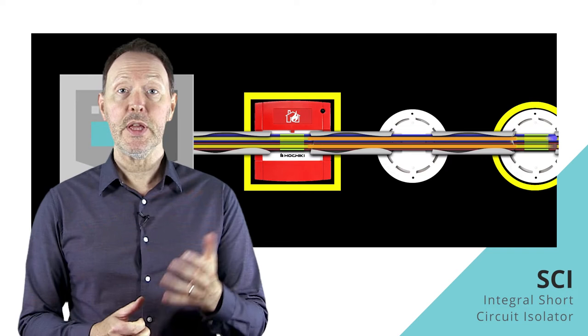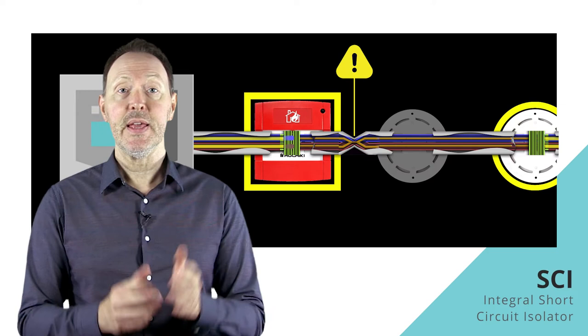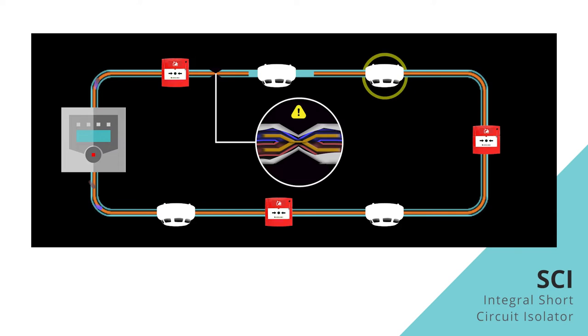If for any reason the voltage level drops below a set threshold, the isolators activate instantly, maintaining the loop voltage for the rest of the loop. So again, let's introduce the short circuit through damage to the loop cable here at this point, but instead of the loop voltage stopping and the panel losing communication with the loop devices, the isolators within these two devices now activate.